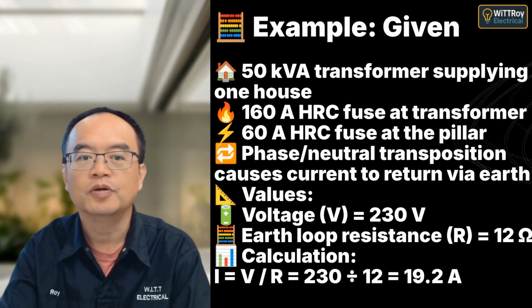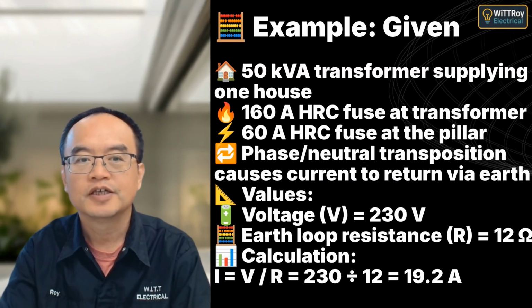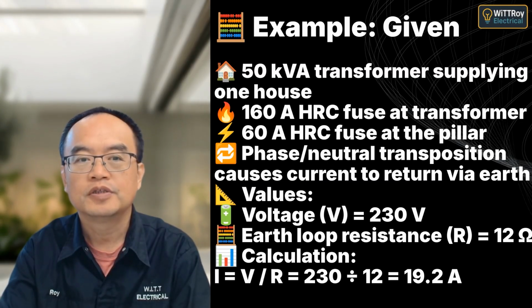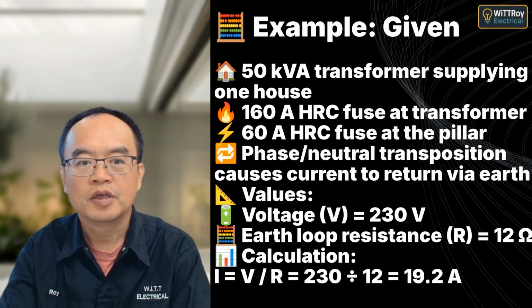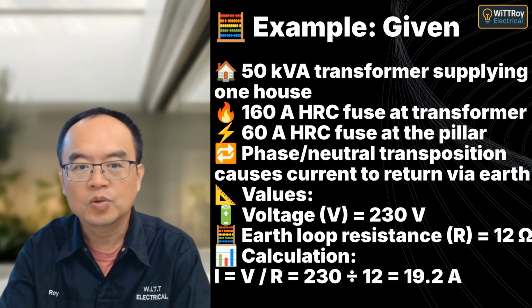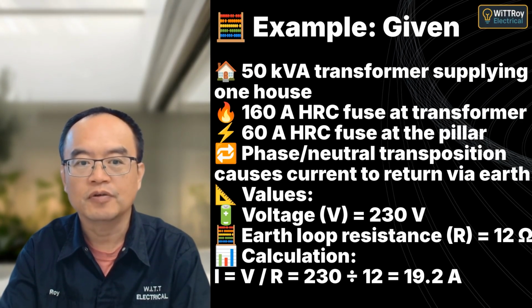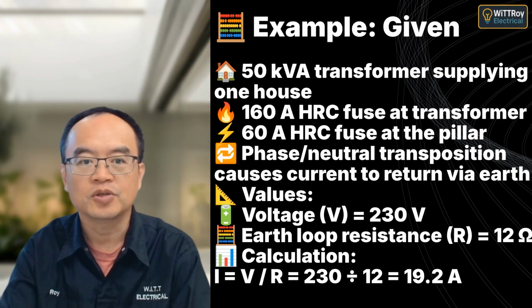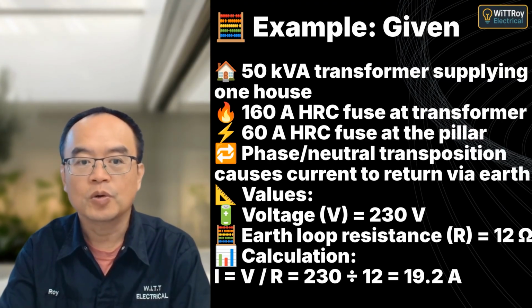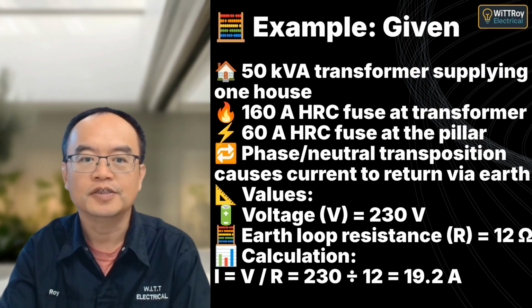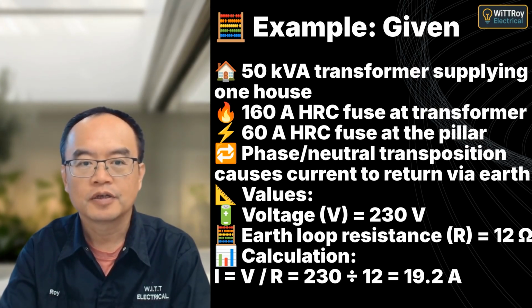In this example, a 50 kVA supply has a 60 amps fuse at the pillar and a 160 amps fuse at the transformer. With 230 volts and 12 ohms earth loop resistance, the fault current is only 19.2 amps. That's too low to blow either fuse. So even though there's a phase-neutral transposition, the supply stays live, making it unsafe. Always test polarity before turning power on.